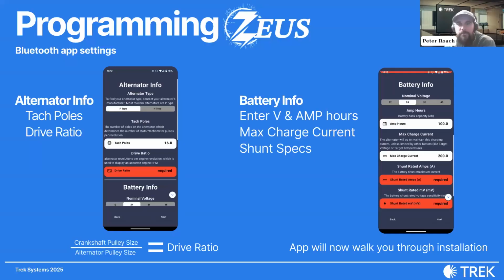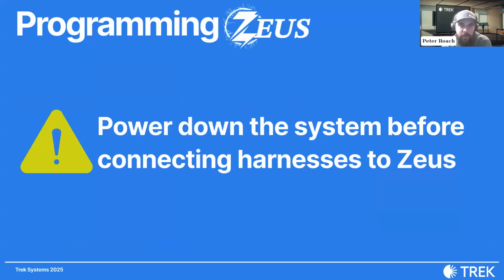On the battery info, set the voltage, amp hours, and the max charge current. Below that, we have the shunt rated amps, the shunt specs, and that'll ensure we're getting the proper readings. Before we connect the Zeus harnesses to the regulator, we want to make sure that the battery system is off, because if the harness is live, there's a potential for an arc when we're plugging it in. This could damage the Zeus circuit board or possibly the connectors. It's an easy situation to avoid, so let's all take this step.